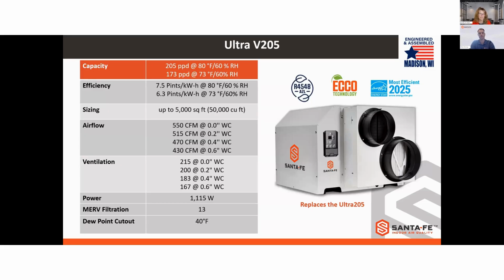Very energy efficient. 6.3 pints at 73/60, but 7.5 at 80/60. It can remove a lot of moisture when running, up to about 5,000 square feet. Where we really see this one utilized is in a lot of light commercial applications. Most of the time in our residential applications, homes that are about 5,000 square feet are going to have more than one HVAC system. So we like to put a smaller dehumidifier on each system, but sometimes we can't do that. So in that application, we would want a bigger unit like this on the main system of the house.